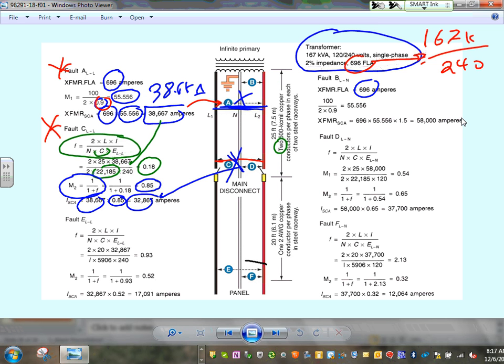Okay, if that's not enough for you, gentlemen, let's go back to another EE. Here's my EE, right at this point. Let's do the formula again. Now at EE, I have 20 feet of one conductor number 2. So when you do that, 2 times 20 feet times the current, divided by the C factor for this conductor, which is this number, divided by the voltage.